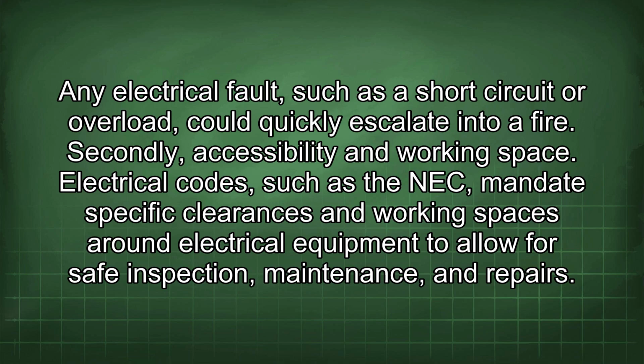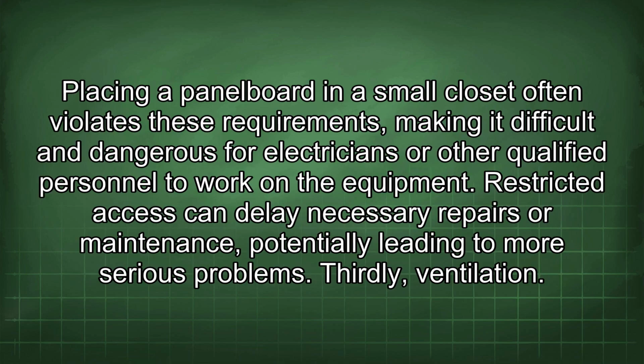Secondly, accessibility and working space. Electrical codes, such as the NEC, mandate specific clearances and working spaces around electrical equipment to allow for safe inspection, maintenance, and repairs. Placing a panel board in a small closet often violates these requirements, making it difficult and dangerous for electricians or other qualified personnel to work on the equipment. Restricted access can delay necessary repairs or maintenance, potentially leading to more serious problems.